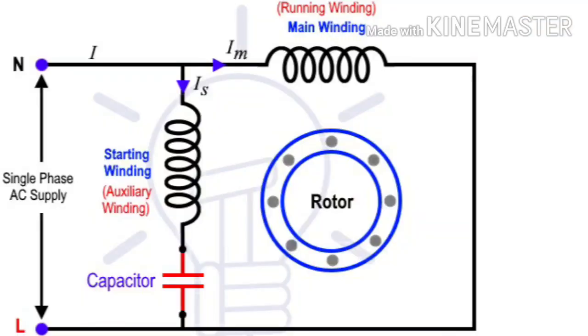To overcome this problem, we use a capacitor in the fan. When we switch on the fan, the same phase enters both the running winding and the capacitor. The phase entering the capacitor gets boosted, and this boosted phase enters the starting winding, while the original phase enters the running winding. Because of these two different phases, magnetic rotation is created, the rotor rotates, and the fan starts.